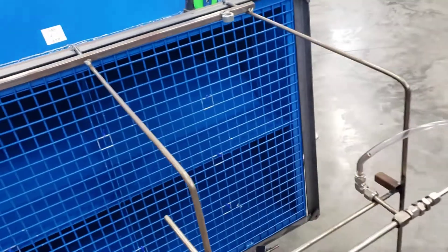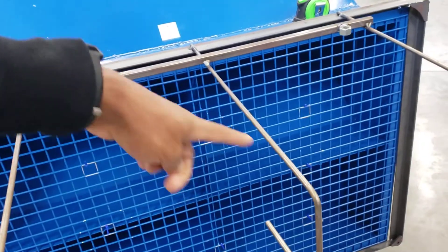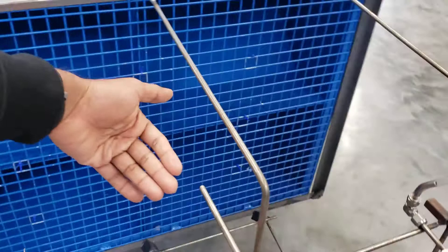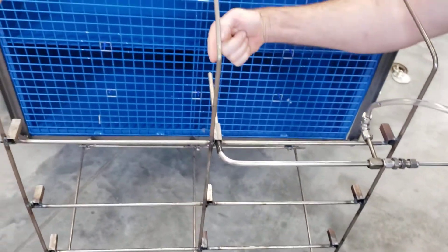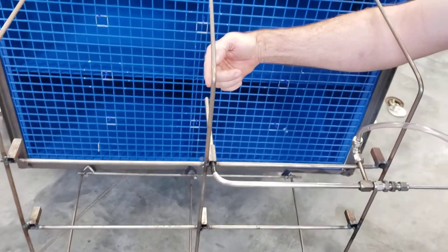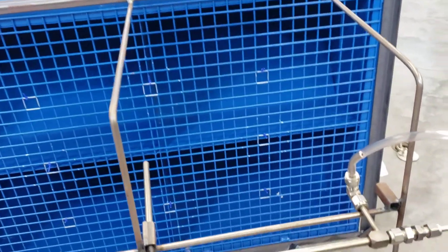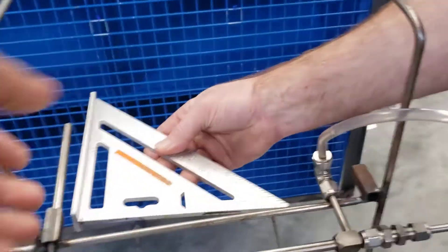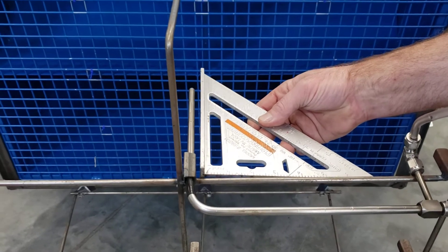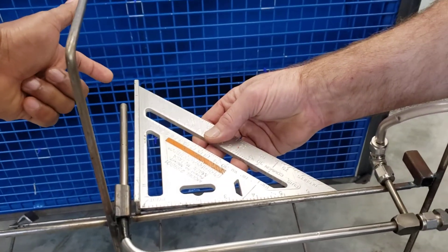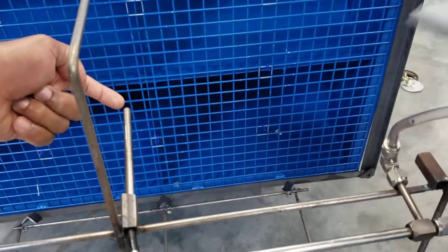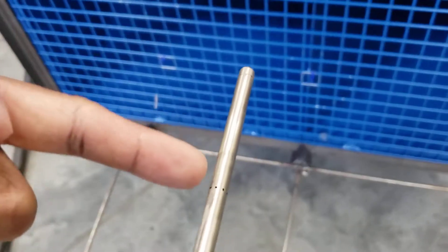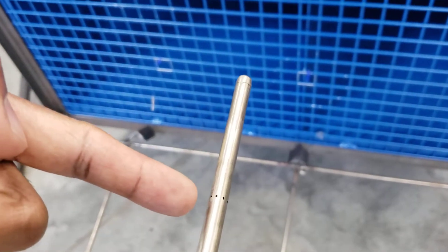The flow is coming from this way and it has to go straight to that tip. This setup will help you place it perpendicularly, as you can see here like this. That way we can make sure that we get all the dynamic flow into the tip, and these small little holes only read the static pressure.